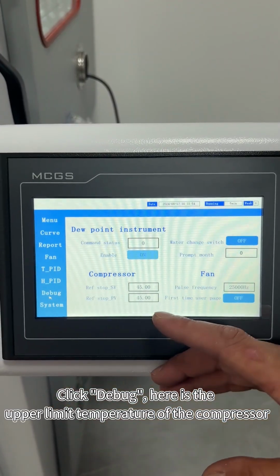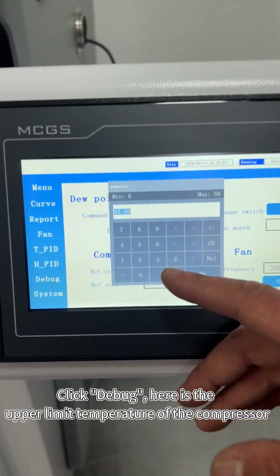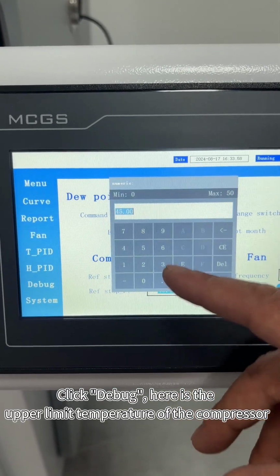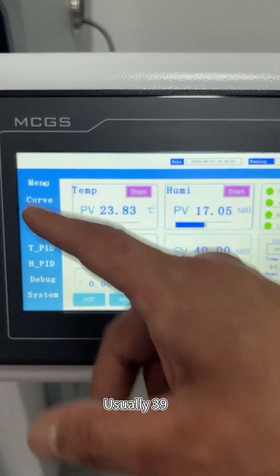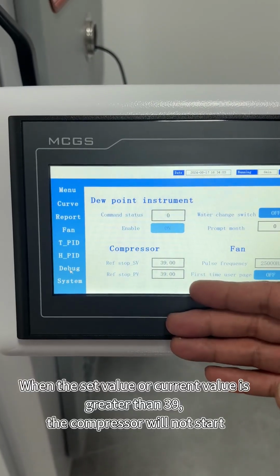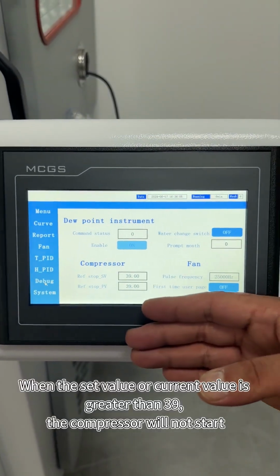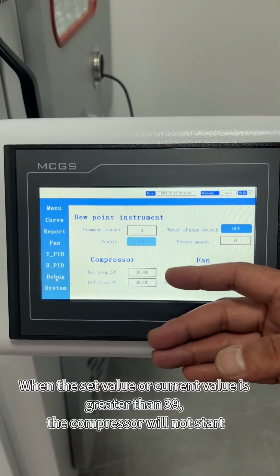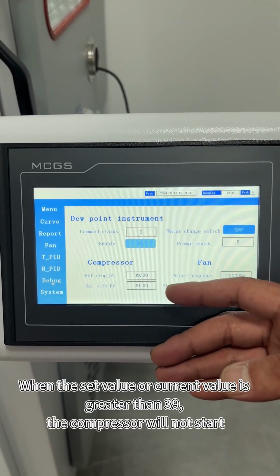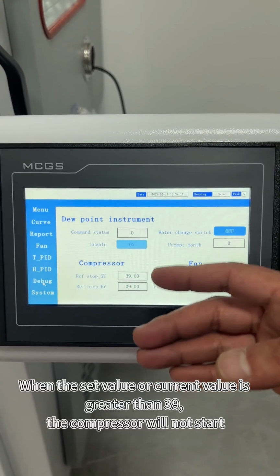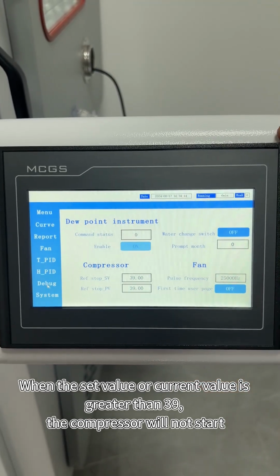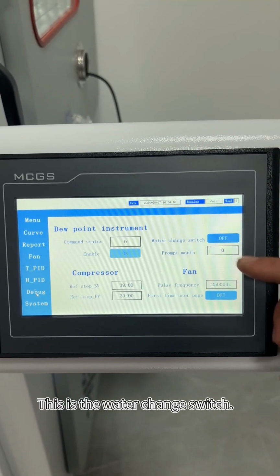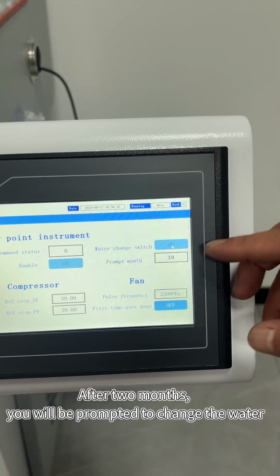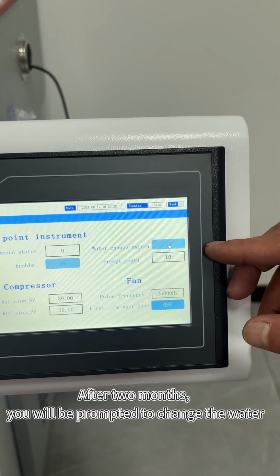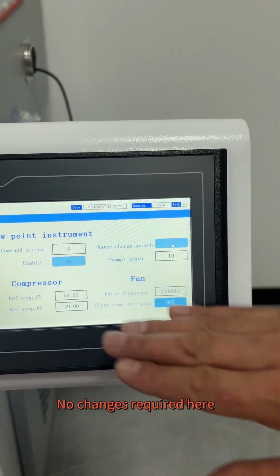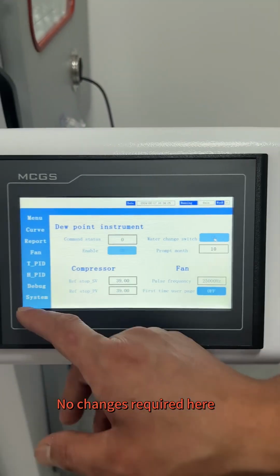Click debug. Here is the upper limit temperature of the compressor. Usually 39. When the set value or current value is greater than 39, the compressor will not start. This is the water change switch. After 2 months, you will be prompted to change the water. No change is required here.